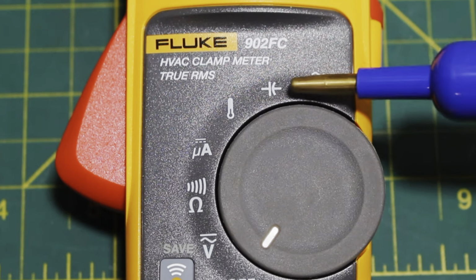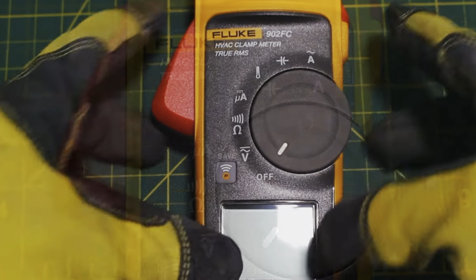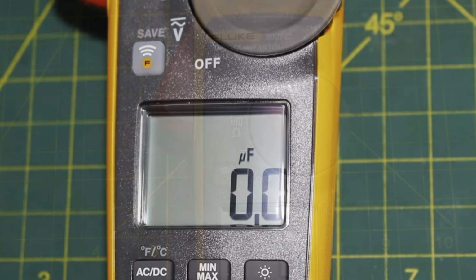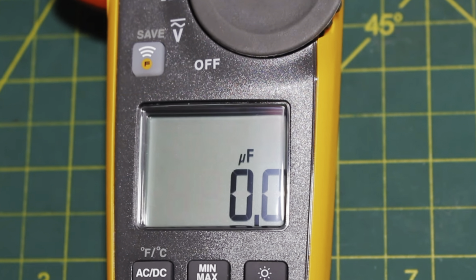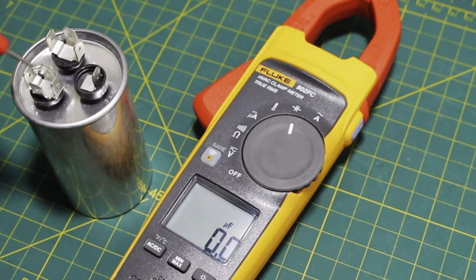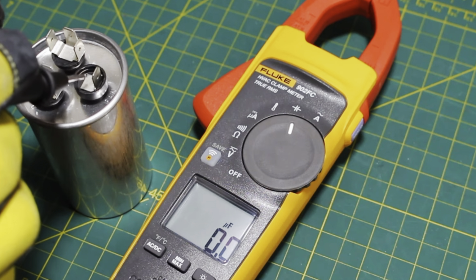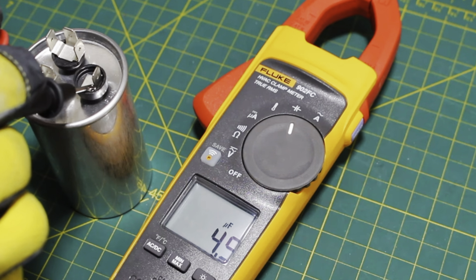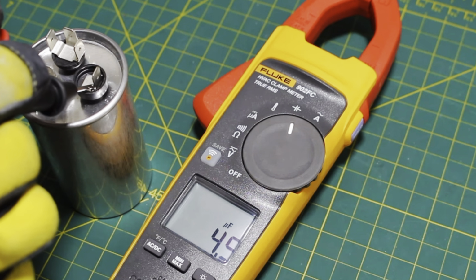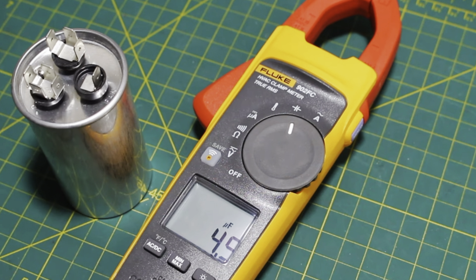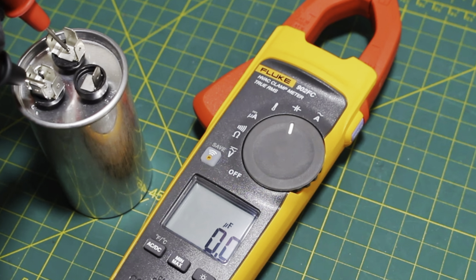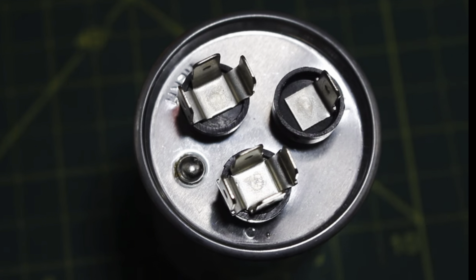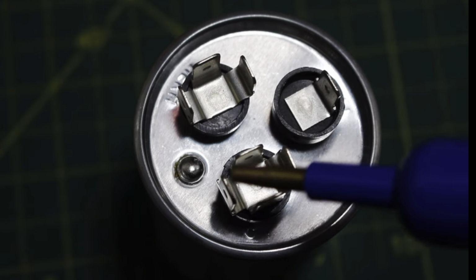Once removed, the capacitor can be tested by this setting here, which is capacitance, also known as microfarads, as indicated by this weird looking U and F. Once on this setting, you can test the leads between common and fan to get the fan side of 5 microfarads, and switch over from common to Herm in order to get the Herm or compressor side at 25 microfarads for this particular capacitor.